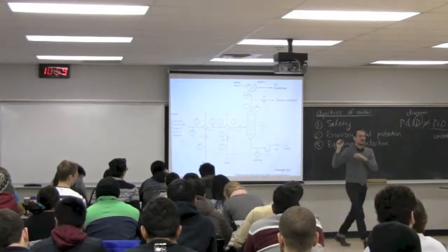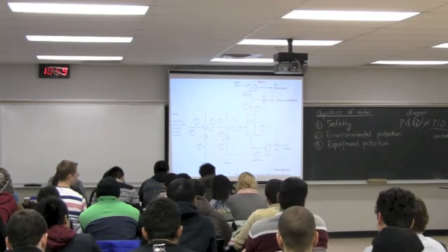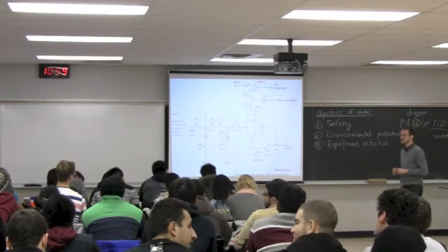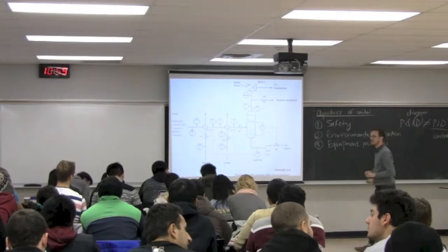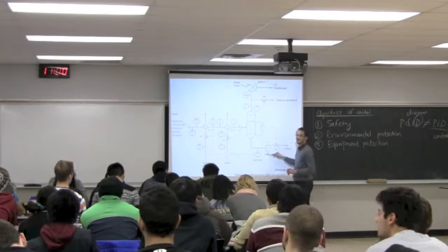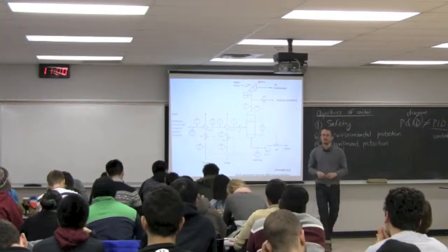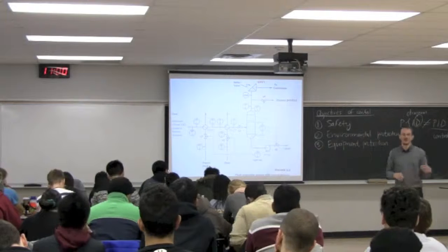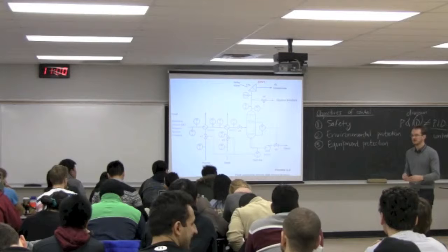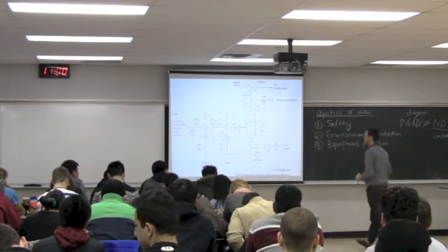Anything else about LC1 that might be protected? That's a good one. Yeah. Any other aspect? Yes. LC1 is controlling the valve B5, and then indirectly controlling the pump, so the pump doesn't run dry and it won't damage the pump. Okay, so we're going to use LC1 as a way to protect our pump. We're going to make sure that there's enough liquid coming in so we never run our pump dry. Some pumps cannot tolerate being run dry. Or for a short period we can, but we can quickly lead it to being damaged if it runs dry. Okay, so LC1 is there for equipment protection.